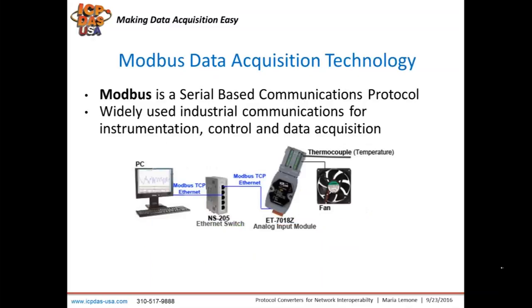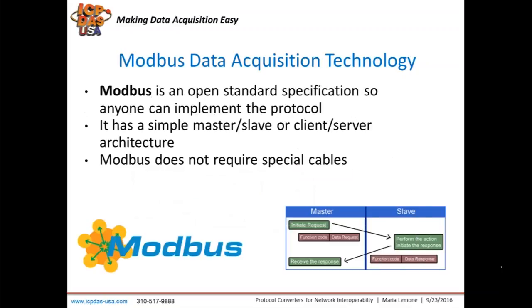They know how to communicate with different devices that communicate over different protocols, as they have memory maps inside them and get data from one device, store it in a table, and pass the corresponding information in another protocol to another device. Process values, temperature measurements, and other sensor data from sensors are continuously updated from a slave device. When the master device using a different protocol needs the information, it will be available in the format it can understand.